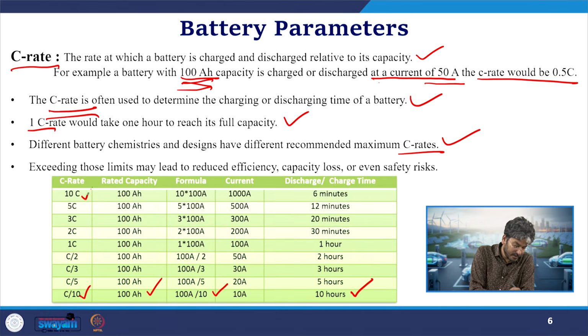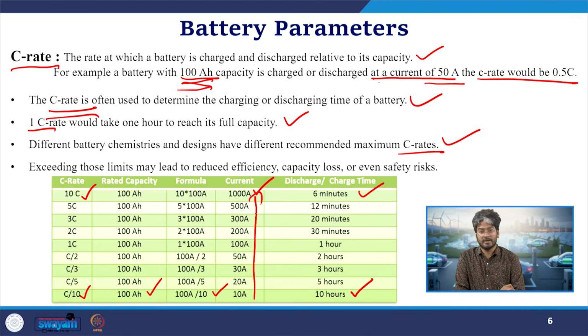Now let's go to the maximum case, 10C. At 10C, the battery draws or dumps a current of 1000 amperes, charging and discharging in just 6 minutes. So increasing the C rate means increasing the current handled by the battery and the BMS system. The charger rating increases because it must handle higher current, and on the battery side, losses increase because of higher current, resistance, and the various series and parallel connections of battery cells and capacitors generally used to model the battery.